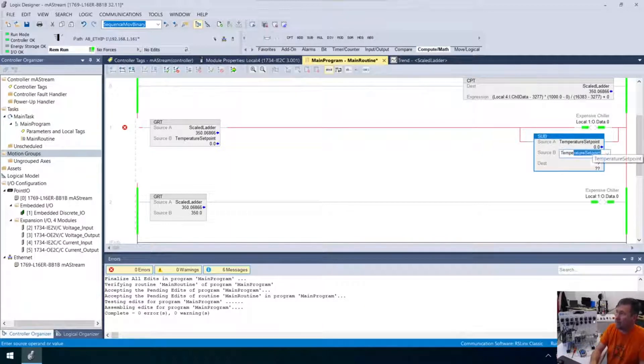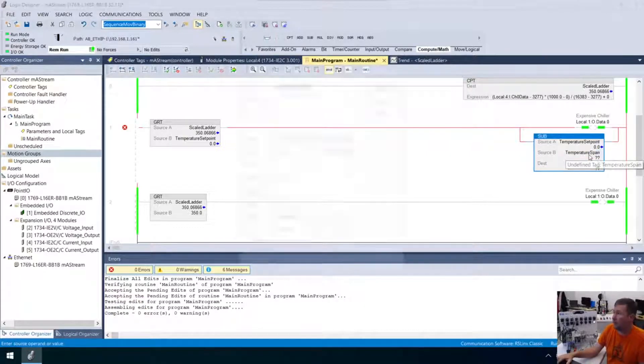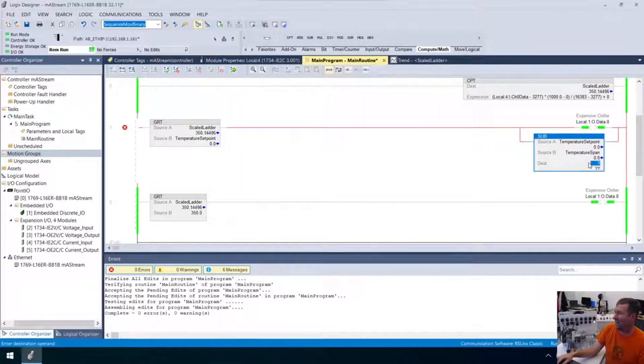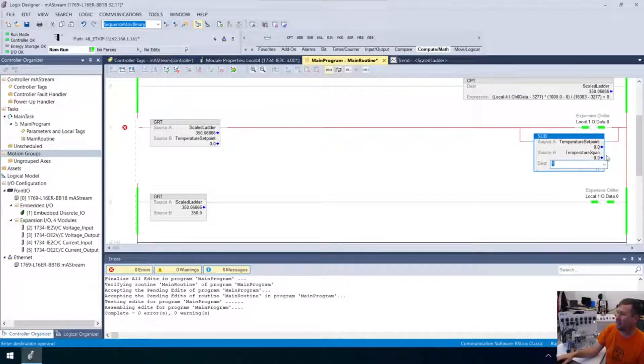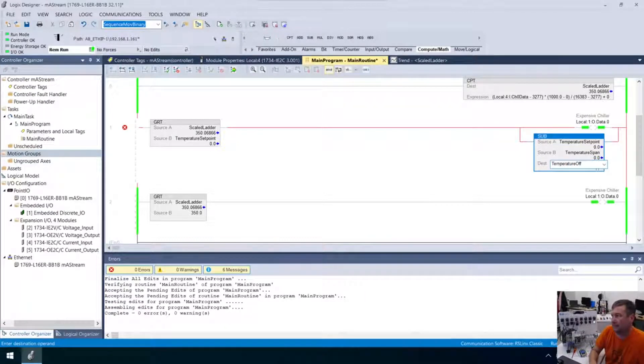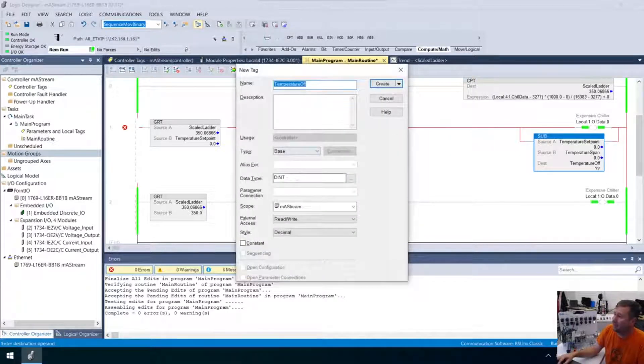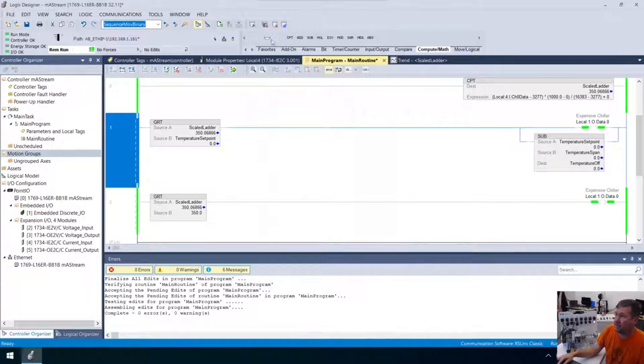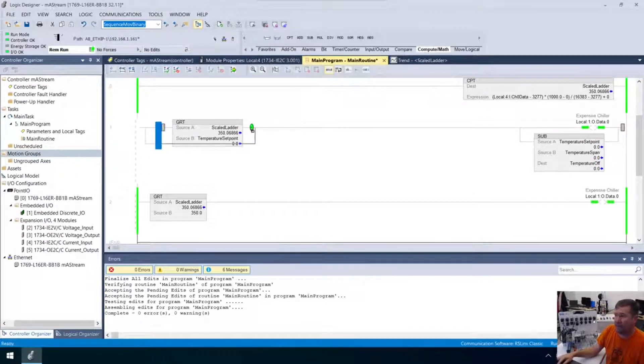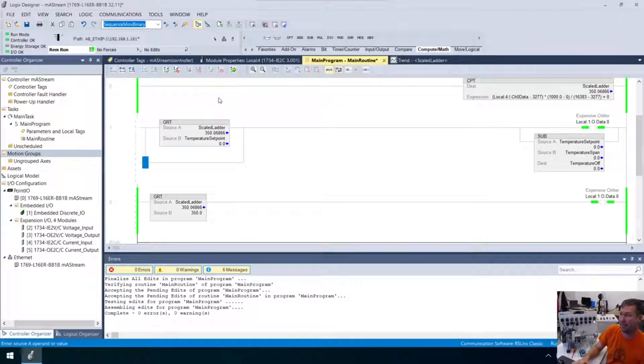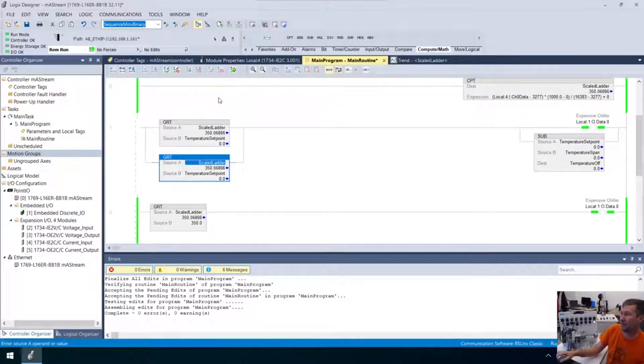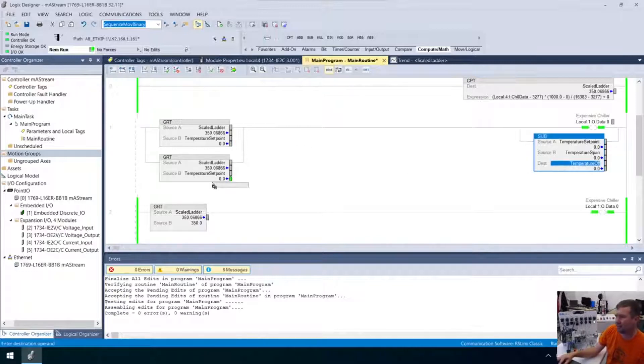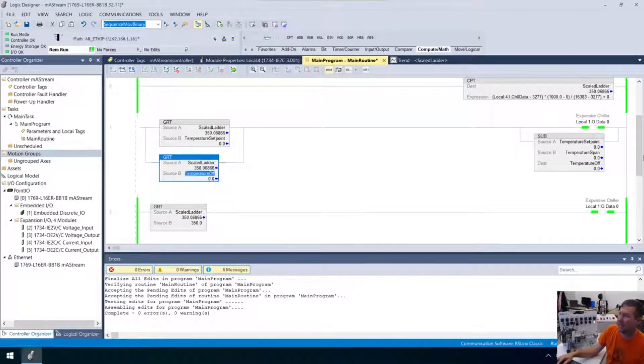Now first, let's go and change this. It's no longer expensive pump. This is our expensive chiller. And now what we're going to do is we're going to go to our math tab and we're going to bring down a subtract instruction. And we're going to take this temperature set point that the operator is entering and we're going to subtract it by our temperature span. And we'll create that as a real number. And then we're going to need, in this case, let's call it our temperature off. That's what I'm going to call it because I can't think of anything to call it right now. And we're going to create that.